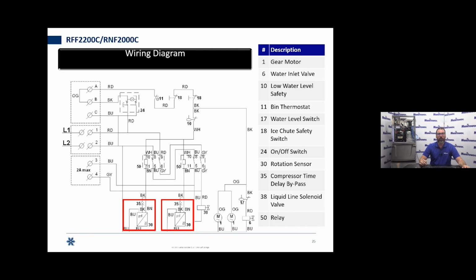Both of them have to be made before that liquid line solenoid relay coil will open. So keep in mind that we have 2 here to troubleshoot, but they are exactly the same in operation. The LED colors, the flashing all mean the same things. It's just that we're going to have 2, and both of those 2 would need to be in their run condition in order to energize that liquid line solenoid.